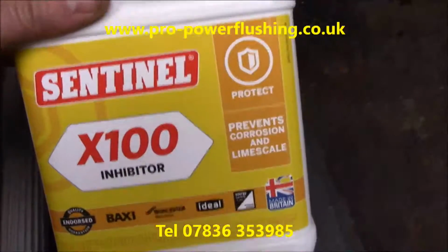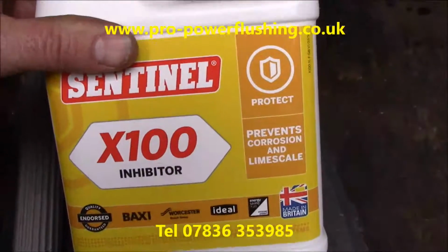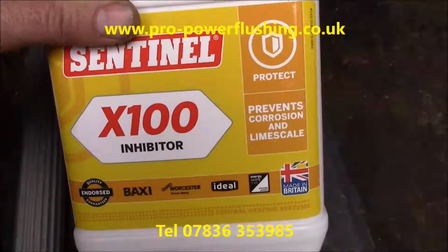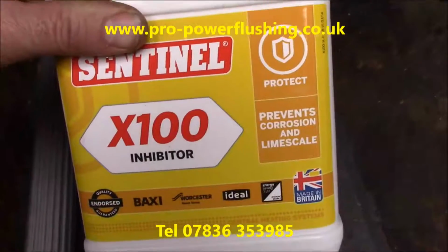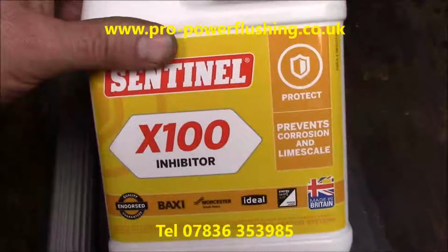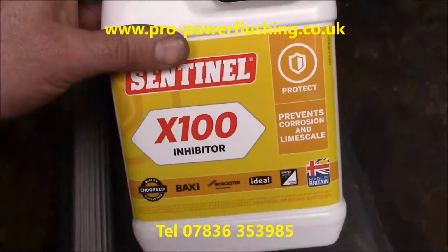This is the Sentinel X100. Because the boiler's in the loft, we're going to add it in our power flush machine. It's all nice and clean out of water. We're going to add it in front of the customer, and then we're just going to let it circulate around for 10 minutes so it's properly in the system. Then we're going to drain down a couple of feet, and then it's in the system. We'll flush the boiler, put everything back together, and the system should be okay. So we'll get back to you later.